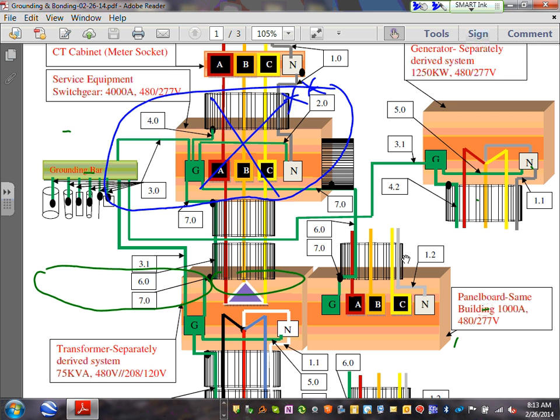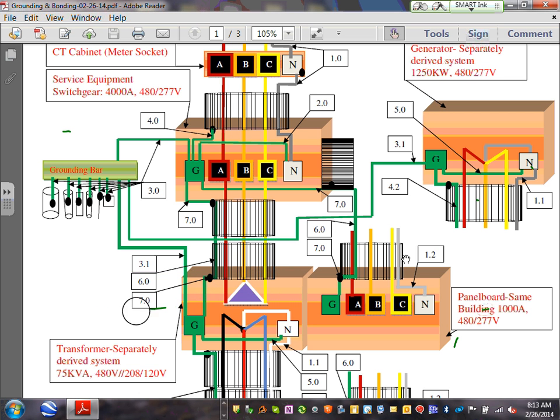Can you guys see that? At the sub panel, right here. So I'm going to move away to equipment, guys, and go to grounding and bonding at a sub panel. I'm going to choose two things then. First, this is equivalent to my mechanical panel. Here's my sub panel. Can you see that right in here? Now, this is a sub panel. That could be a 200 amp sub panel here. The example that I'm giving you is a 1000 amp 480/277 sub panel. Can you see that?